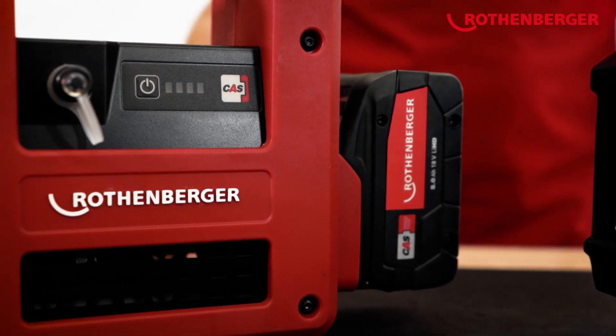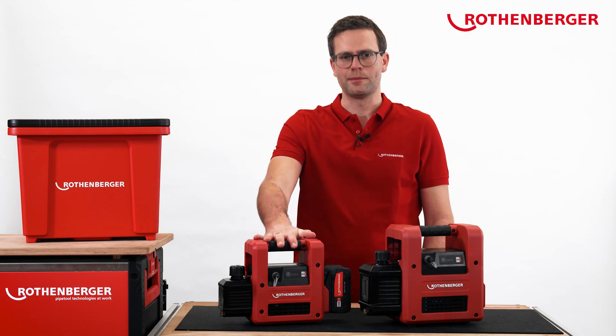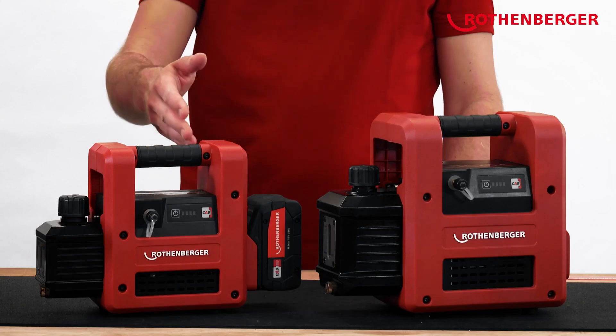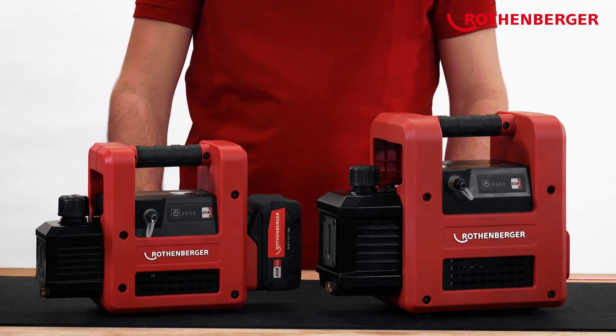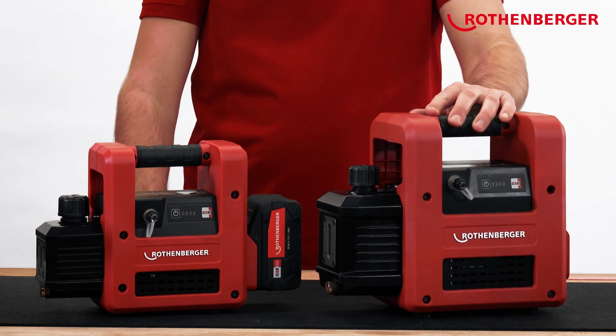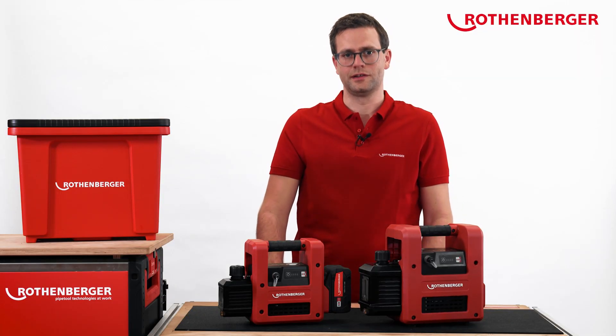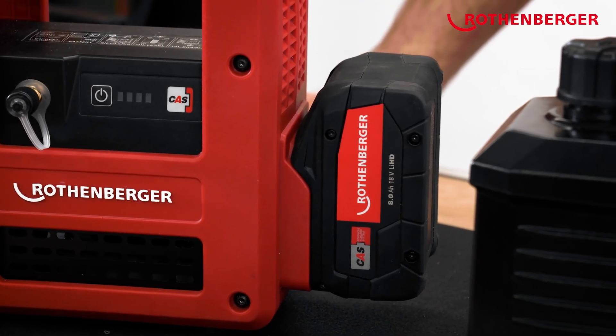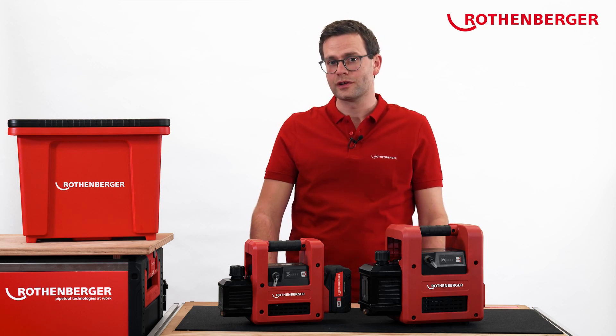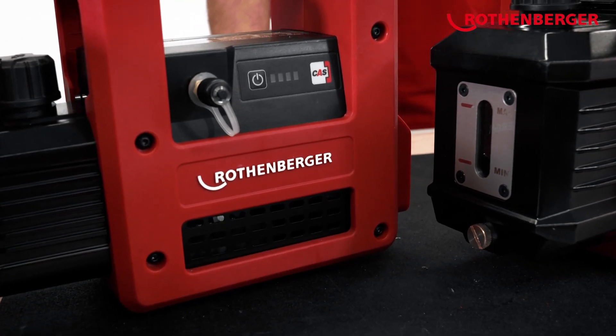The vacuum pumps are available in two different versions. The ROAIRVAC R32 2.0 CL has an output of 57 liters per minute, making it ideal for split air conditioning systems. The ROAIRVAC R32 5.0 CL is ideal for larger refrigeration systems, with an output of 142 liters per minute. The 8 ampere hour CAS battery included in the set supplies the pump with power for up to 90 minutes of running time, meaning you can evacuate several systems with one battery charge.